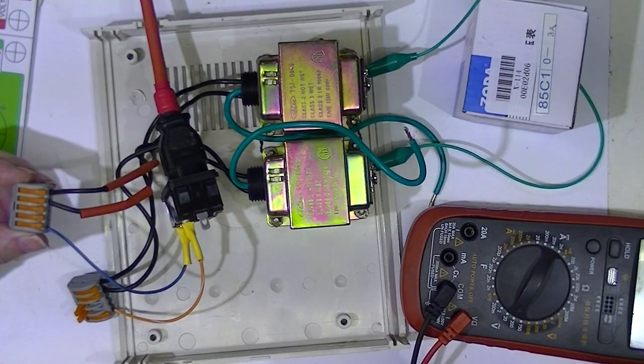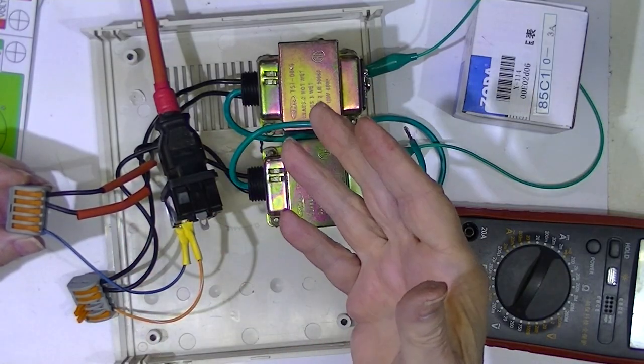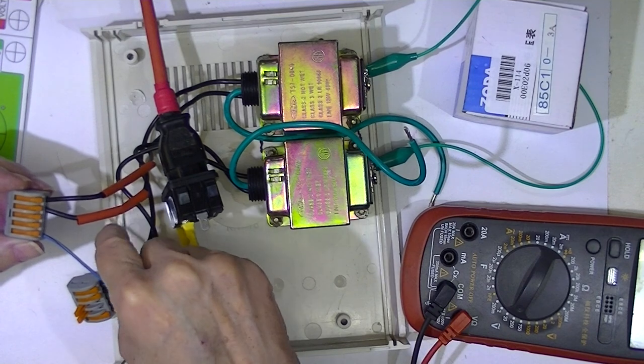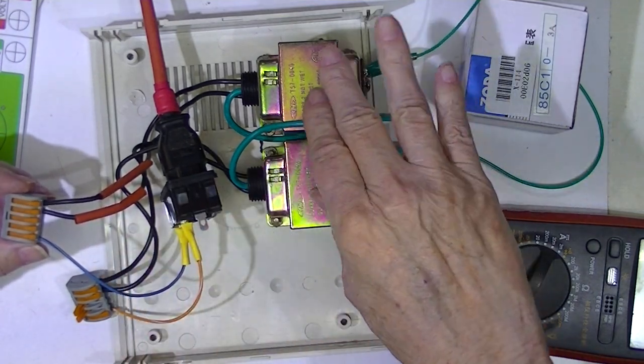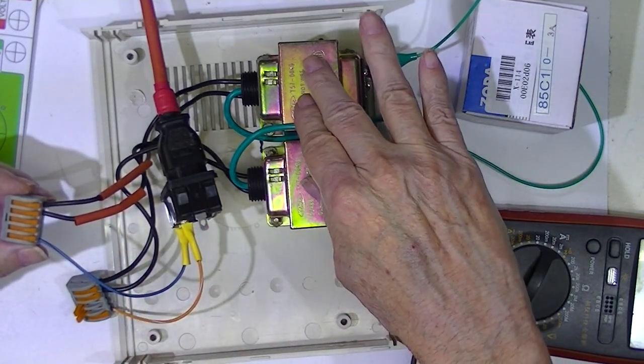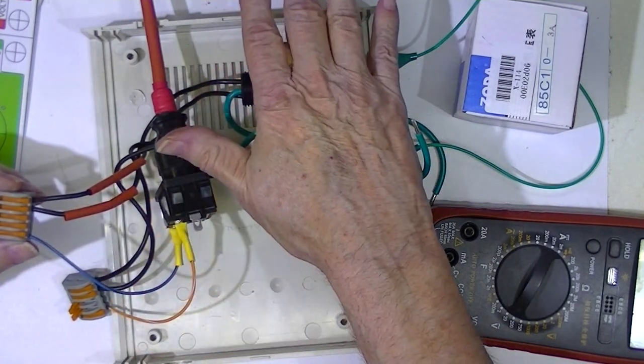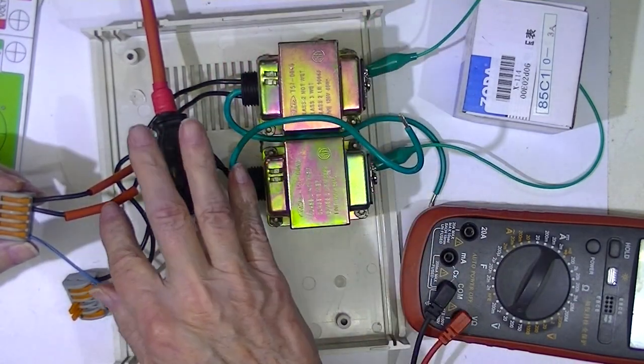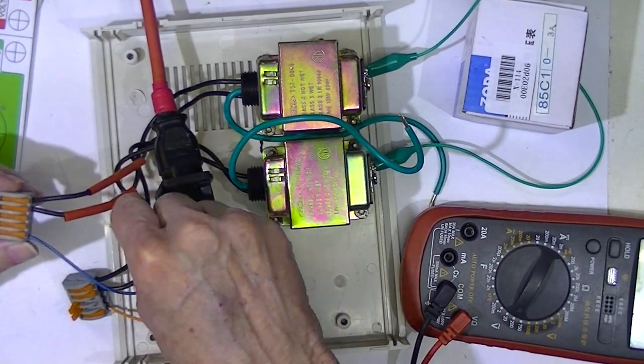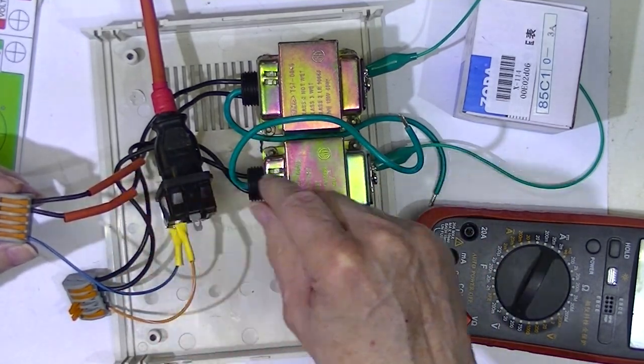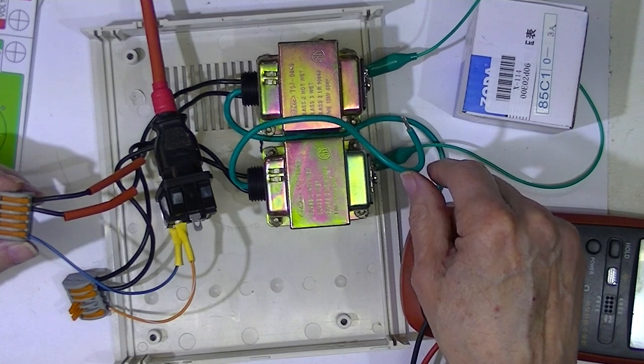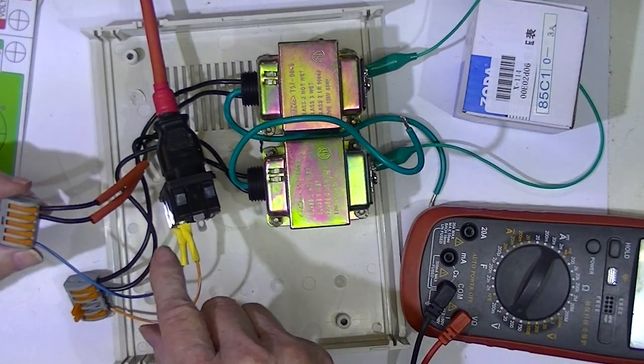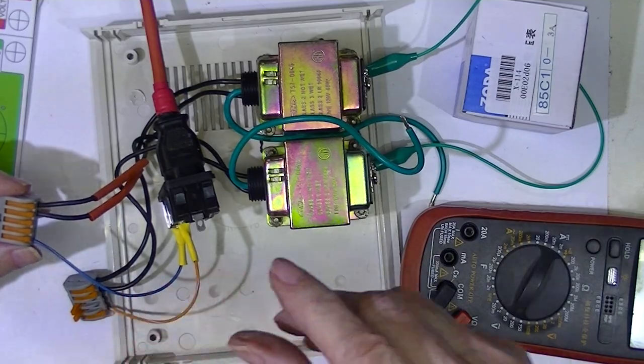The question is, what is going to happen now? And I have a tenth of a volt. In other words, the voltage across these two terminals is very, very small, which is what I want. So let me do a little color coding and I'll be right back. So I took the two - and I don't know which two they are, I just know that these two, when connected together, phase these transformers correctly - and I've put some red heat shrink on them. Now they're not tight. I'm going to slide it up and heat shrink it. But the correct ones.